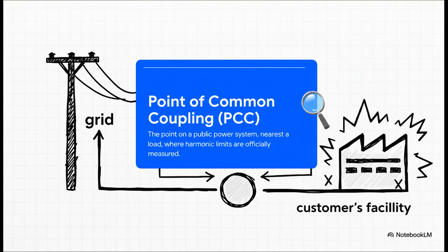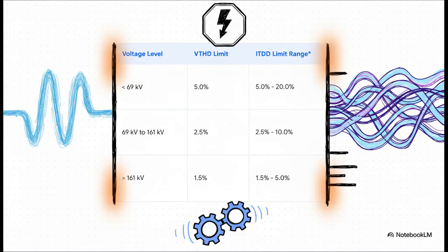To enforce these limits, you need a line in the sand, a place to take your measurements, and that place is called the Point of Common Coupling, or PCC. It's the official boundary where the utility's grid meets a customer's building, where the power company can say: right here, at this point, your electrical pollution cannot go over these limits, period. This table gives a pretty good idea of what those limits look like.